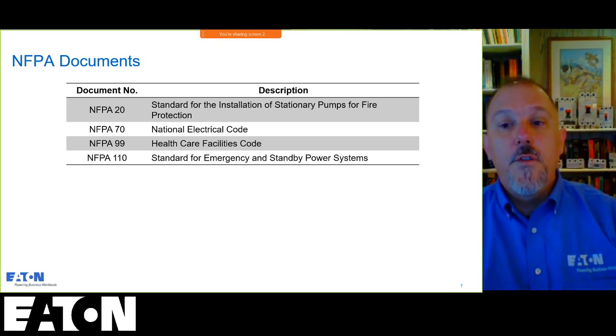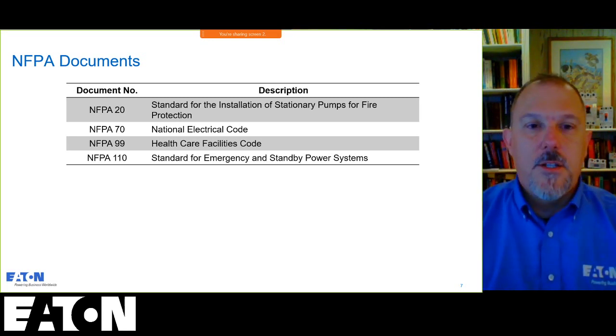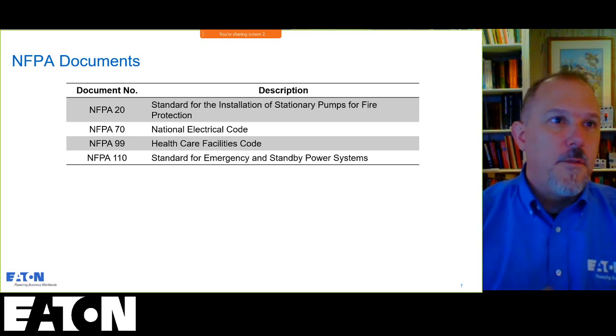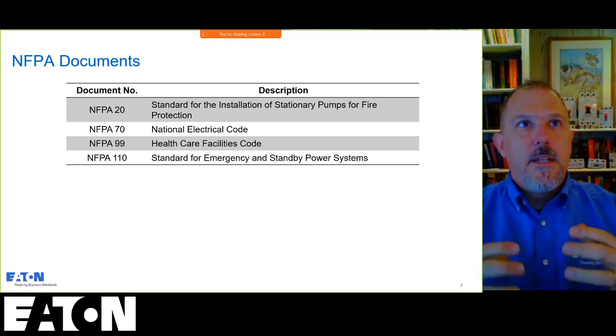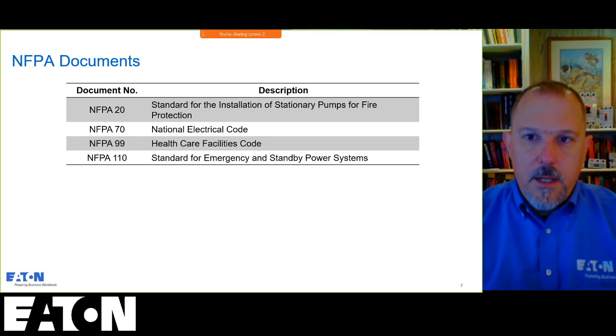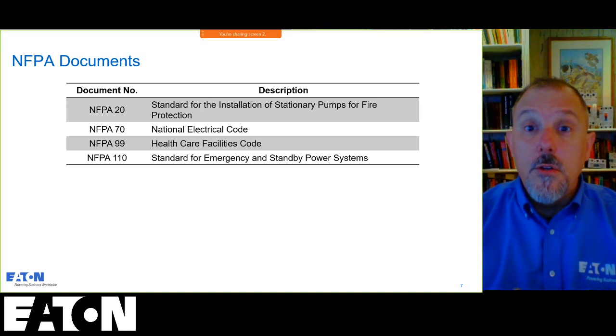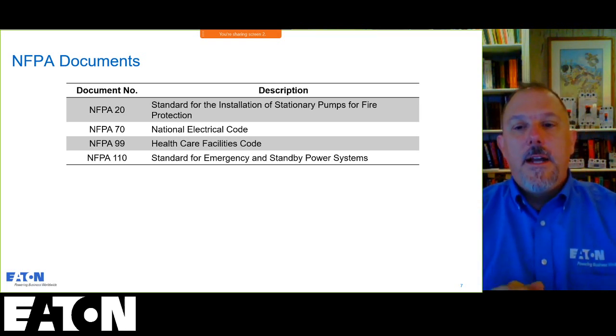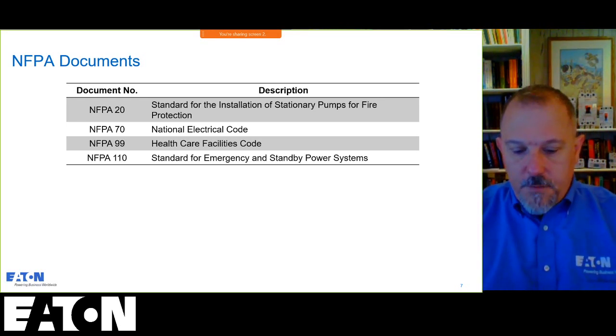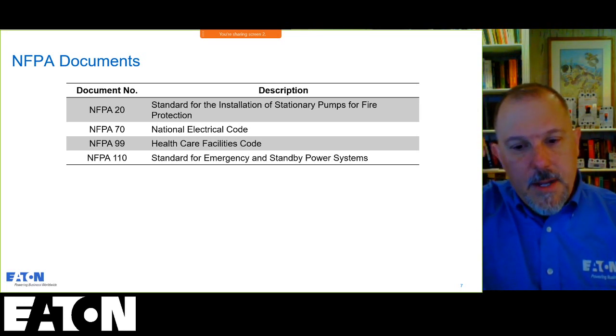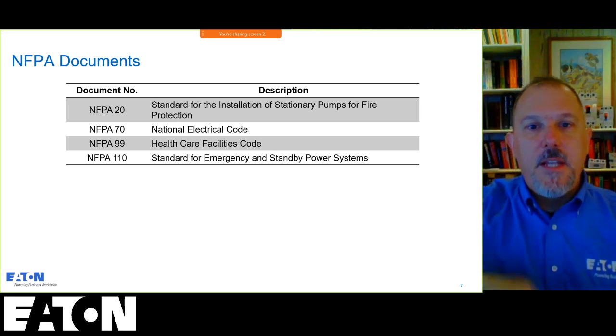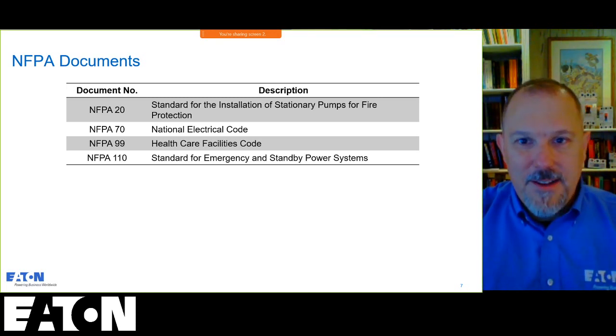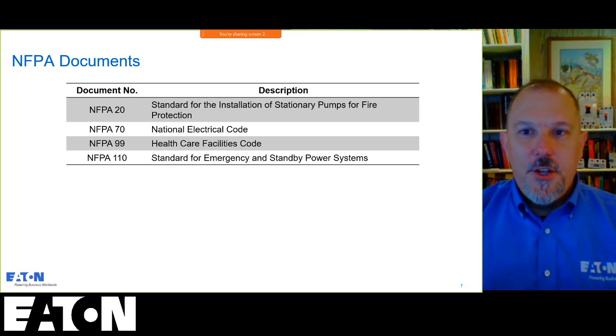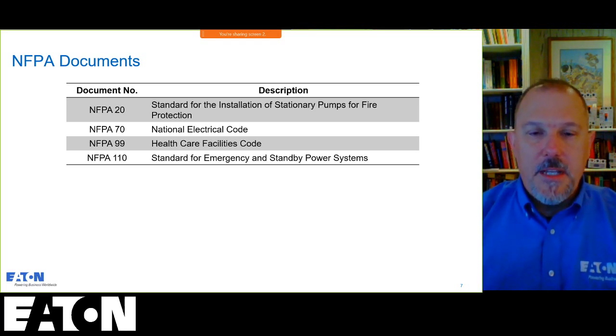NFPA 30, thank you, Kevin, for fuel storage, and the International Fire Code. Exactly. Another important thing, I know in New York, I know we got some people from New York that can maybe comment on this. Remember the hurricane and the enormous flooding issues that we had in New York a few years ago? That drove a change in New York City's standards. I know in Hurricane Sandy, yes. I remember talking to the chief electrical inspector at the time, and he was talking about the design changes. They were putting the generators out of the basement up onto higher floors, but the fuel was still down on the bottom. And that presented a challenge because they moved the generators up for emergency power for obvious reasons, to get them out of the basements, which were flooding.